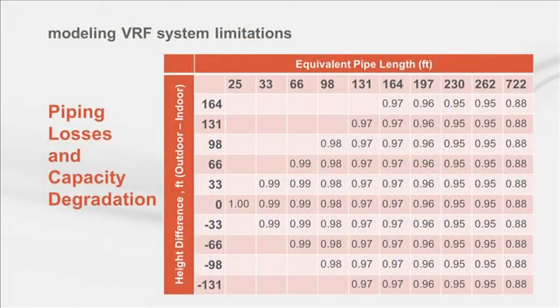Earlier I mentioned that VRF system piping can be quite long. As with other fluids, losses are incurred throughout the piping system. Some simulation programs include losses from the piping, while others do not. With large piping lengths, the total system capacity can be reduced, and this may not be included in the simulation program. Each manufacturer has their own degradation information, so the modeler may need to manually account for this. You can see an example of the capacity correction coefficients for the heating mode from one manufacturer in the table.